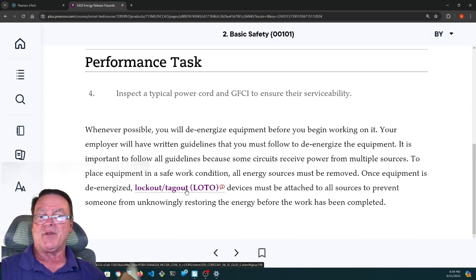Maybe the battery just gave up the ghost. The batteries just went dead. Who knows? Maybe you set it down and then you picked up the wrong one and it doesn't have a working battery and it tells you that everything's a-okay and it's not. So after you check it and it's dead, you have to recheck that meter on a known live circuit. They call it a live-dead-live test. You check it, it's live. You check it, it's dead. You check the meter on another known live circuit to make sure the meter's still okay. Like I say, there's like 7 steps to doing this. You don't just turn it off and put a tag on it.